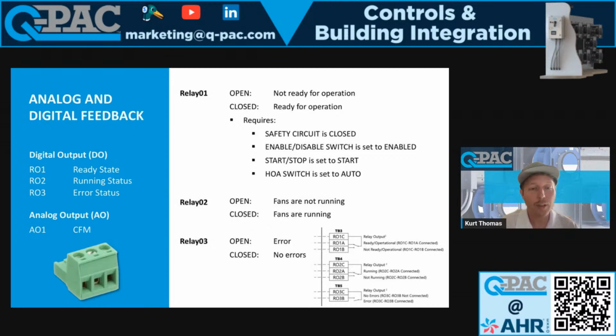So relay number 3, it's just a binary output. It's saying, hey, you don't have any errors with your system, or you do. So if it's closed, then everything's operating nominally. And if it's open, then you have at least one error. If you're not monitoring that error via BACnet, then you can go to the HMI and see exactly what that error is.